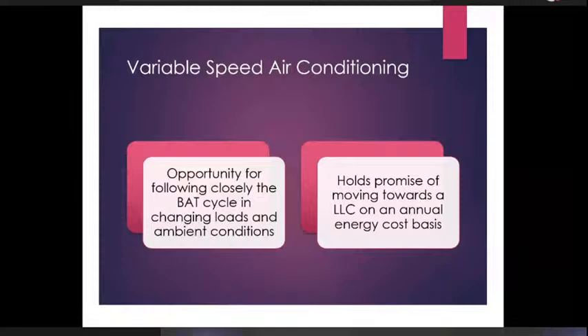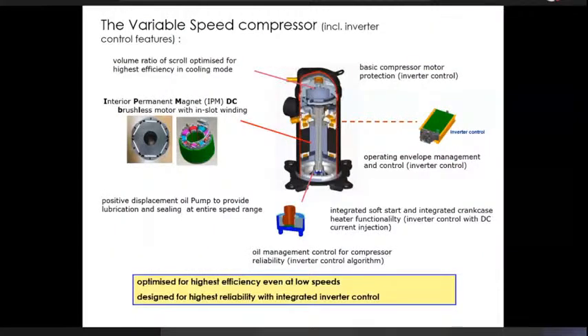These things happen because of varying loads leading to high discharge gas temperatures, particularly in scroll compressors. That can happen because of short durations of high superheat being encountered when the load changes from part load to full load, and there is a delay in the refrigerant being available to the coil. So oil management inside the compressor becomes a big technological challenge we need to be aware of, and then we innovate. We create solutions to that.